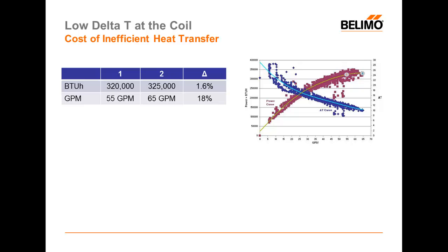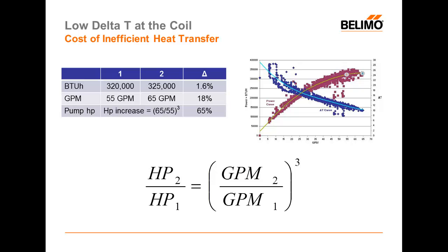So the question becomes: how much money does it cost to pump 18% more water? The pump affinity law tells us that we have to cube our flow increase to calculate the horsepower increase. That means it takes 65% more pump horsepower — or 65% more dollars — to increase our BTU by less than 2%. As you can see at the very high end of this coil curve, the last few percent of BTUs are very expensive.